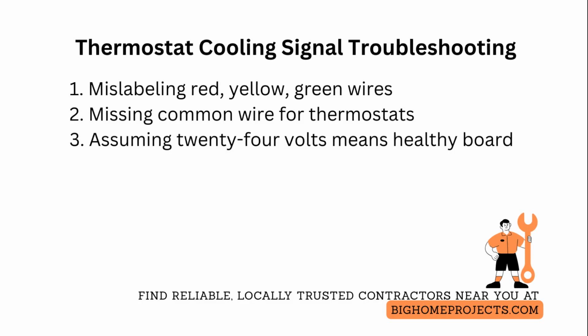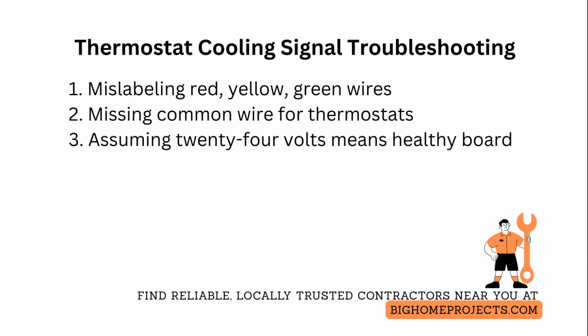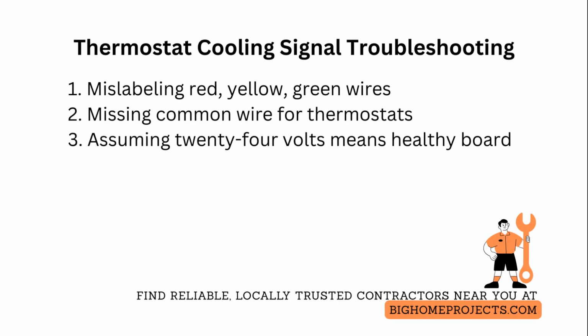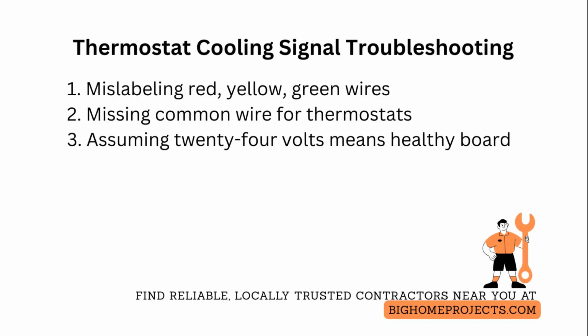Another common issue is a missing common wire causing new digital thermostats to fail or behave erratically. The solution is to install a proper common conductor from the air handler transformer or add a manufacturer-approved power adapter kit.